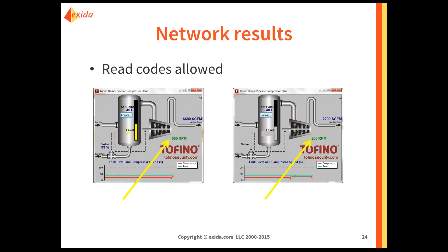We're going to look at some actual network results. This is looking at a small HMI developed to demo the Tofino. The yellow arrows point to the fact that I've changed the RPM of the output side, which causes more demand on the input side. I actually see the demand change and my RPM numbers change. This tells me I'm reading the device correctly and getting a response to my Modbus messages. My deep packet inspection settings for this function code are in place and working correctly.